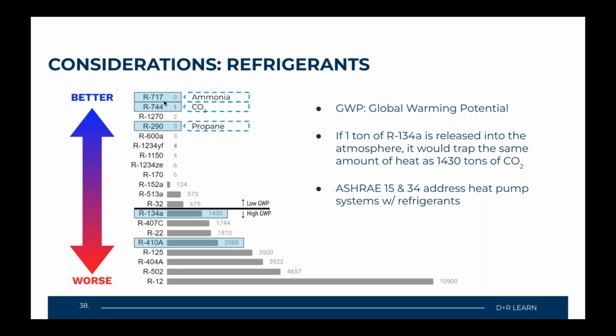But these refrigerants moving up here, from R32 to R717, are better for the environment, and also more common refrigerants that are being used today in order to save energy and also cost. Now, I just want to point out, you can see here we have R744, which Kristy spoke about earlier, CO2, but you also have R717 ammonia and R290 propane. I know propane is not being used in the United States currently, but ammonia and CO2 are the two refrigerants that are being used and are showing very low GWP when in use.